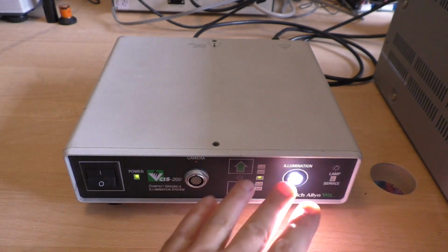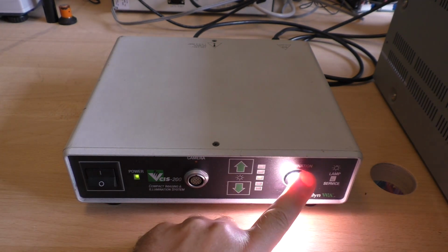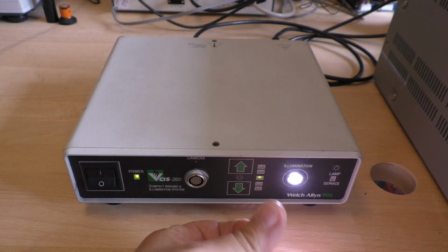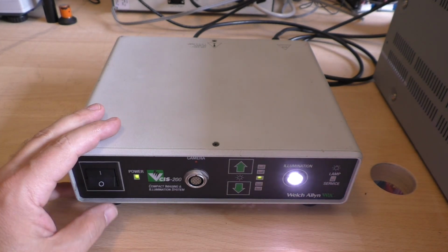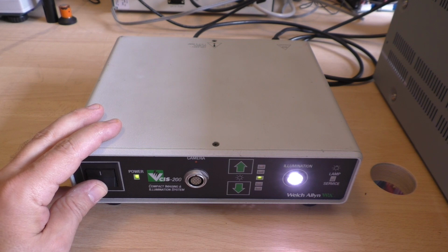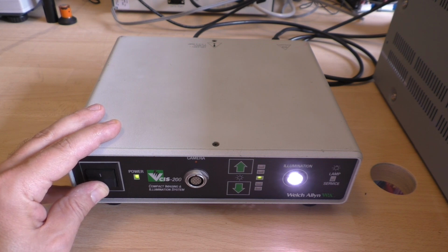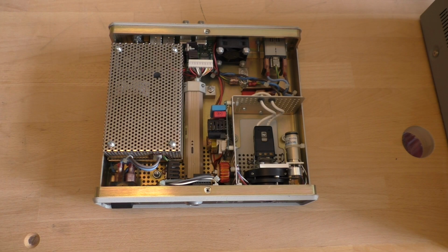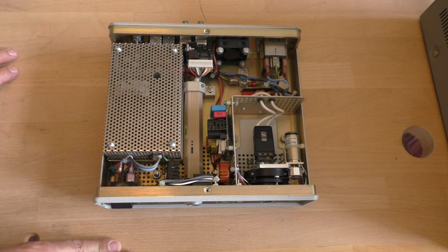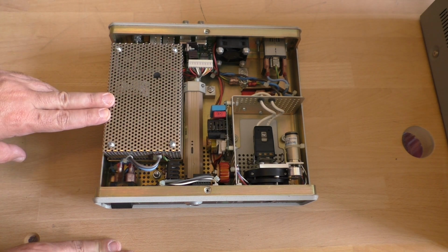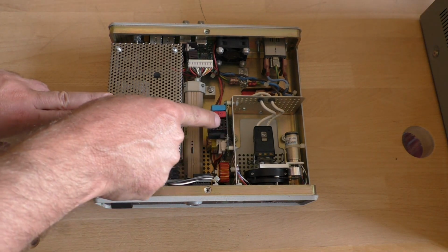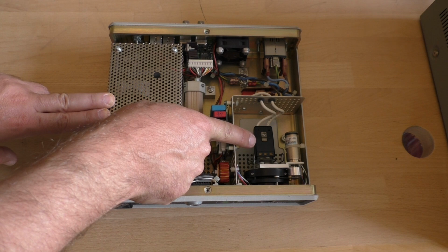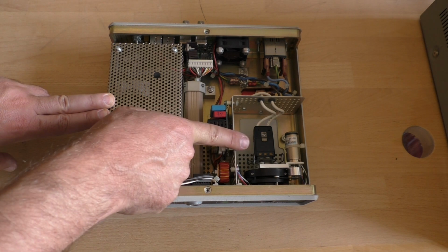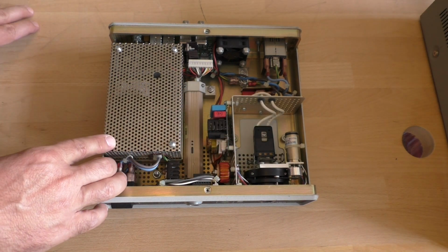I already unplugged the cables from this box, and you see the light is just shining out here, and it gets a little bit warm because it's very intense light. I would suggest having a look inside. I'm pretty sure you want to see how that works. Alright, that's the camera module light source device, and it's pretty simple inside. We have a large power supply. We have an extra power supply for the xenon lamp. It's a short arc xenon lamp with about 30 watts or something.